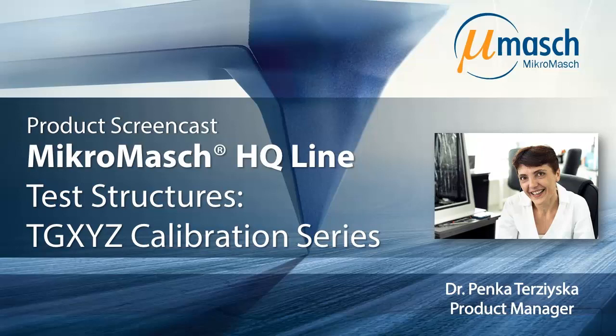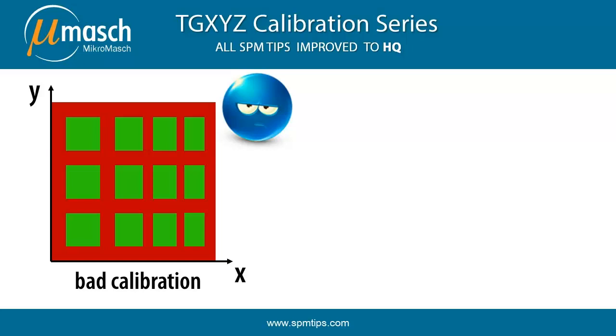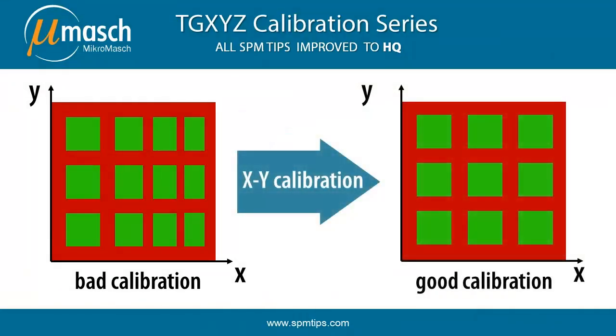In this screencast I will present the MikroMasch TGXYZ Calibration series. In order to obtain accurate dimensional measurements, we have to make sure that our AFM scanner is properly calibrated in X, Y and Z direction. Here is an example that illustrates the distortion of the topography image when the X-axis calibration is wrong and its correction after the calibration has been done.